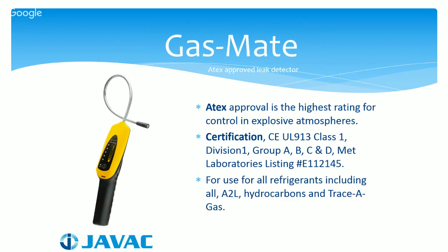The ATEX approval on the Gas-Mate covers EN 60079 and EN 60079-15. This makes the Gas-Mate compliant to use in explosive gas atmospheres. So for using leak detectors for R32 and hydrocarbons, we highly recommend that ATEX approval should always be the standard. The Gas-Mate is classified at UL 913 Class 1, which is the standard for intrinsically safe apparatus.